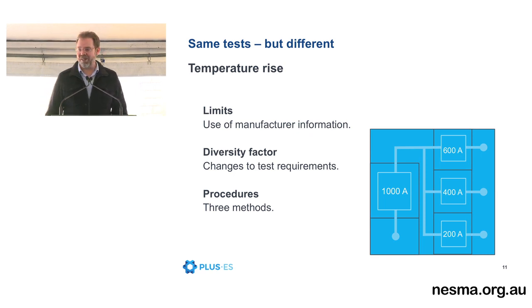Diversity factor is different. So in AS3439, let's say we had an 800 amp outgoing circuit breaker functional unit. Now you could apply a 0.75 diversity factor to your outgoing units, and so what that means is you would have an 800 amp outgoing unit that you can only run 75% of. 800 is going to be 600, oh my goodness, 600 amps.